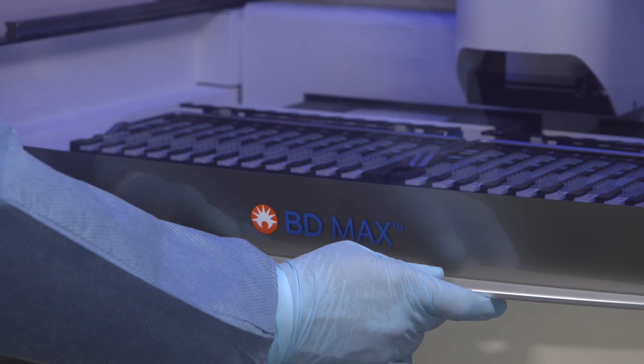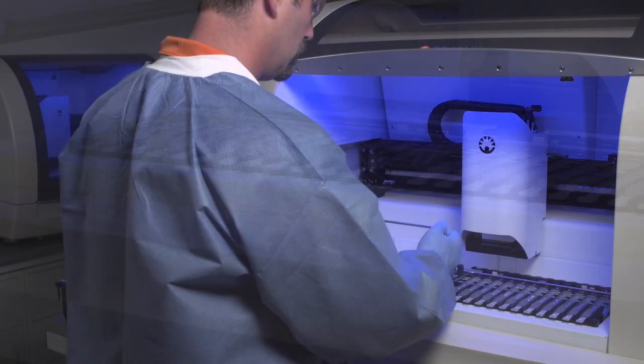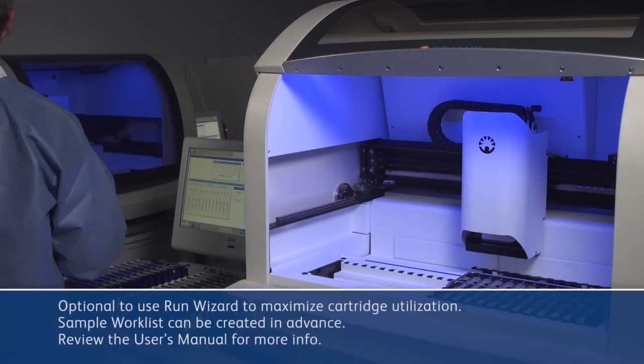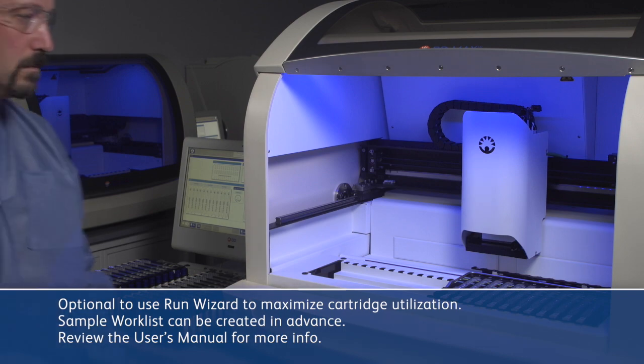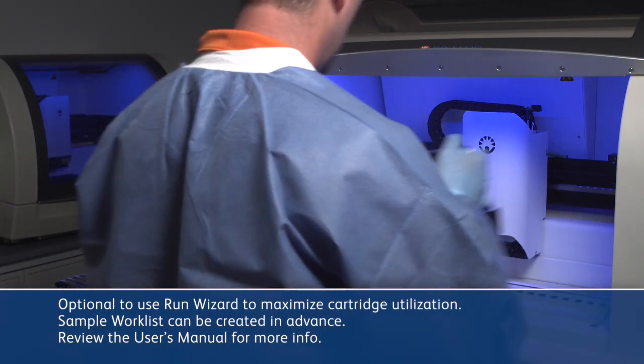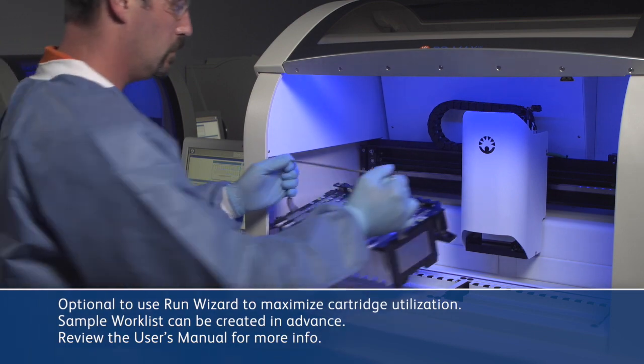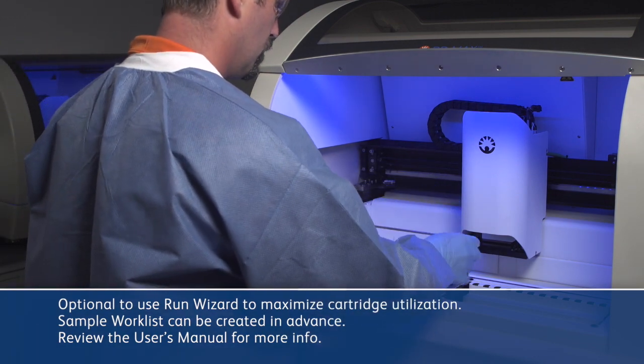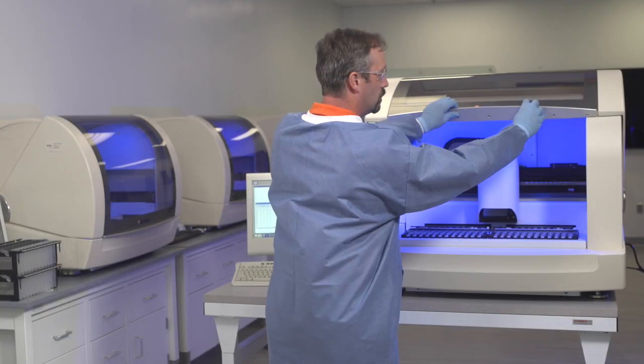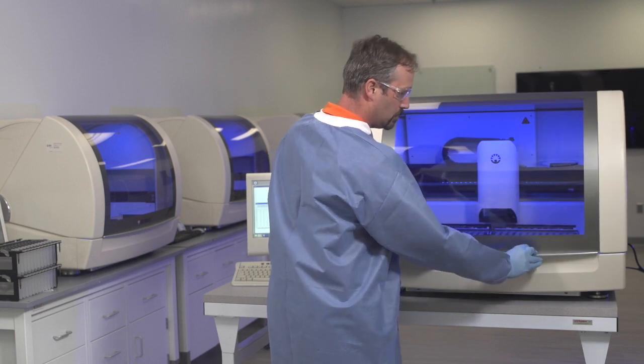Then open the door and remove the rack or racks from the first run. Enter the information for the second run into the worklist if needed. Load the racks containing the sample buffer tubes, reagents, and unitized reagent strips for the second run into the instrument. Close the door again and click the start button.